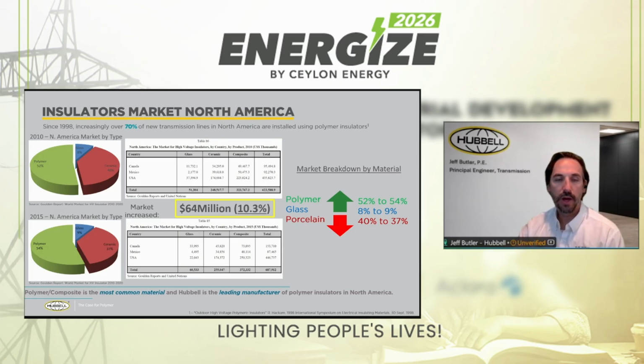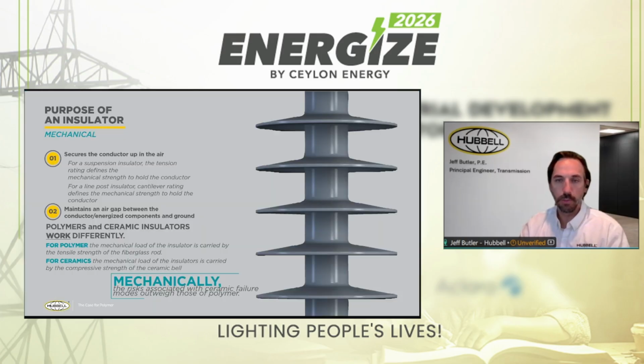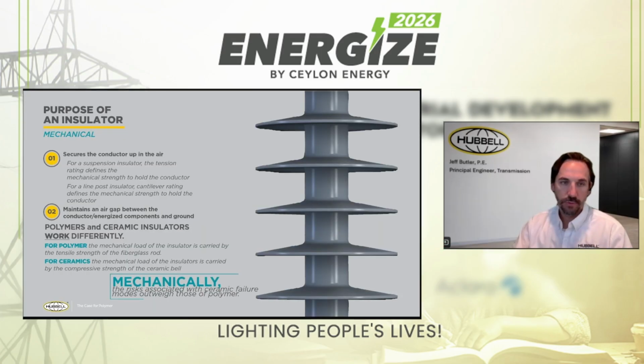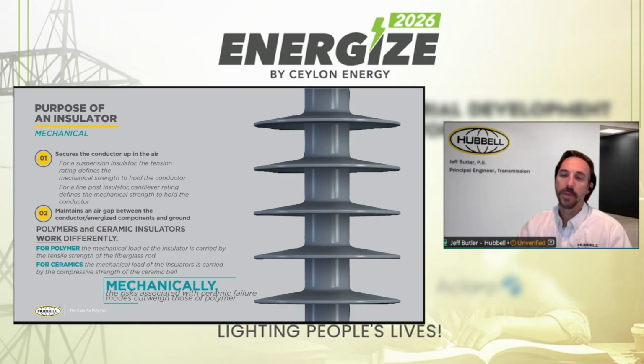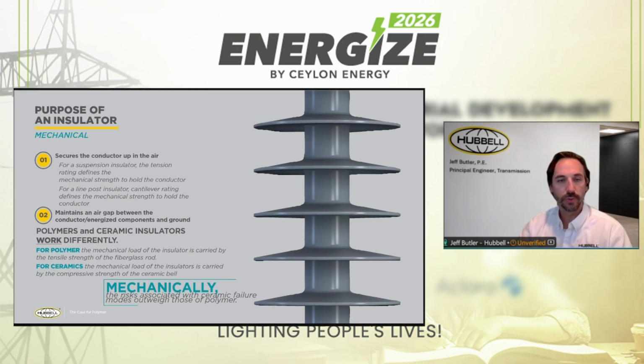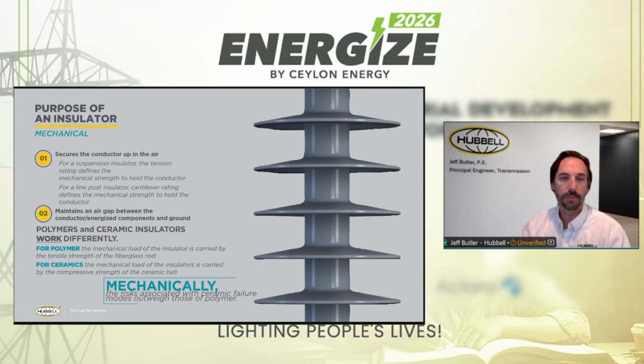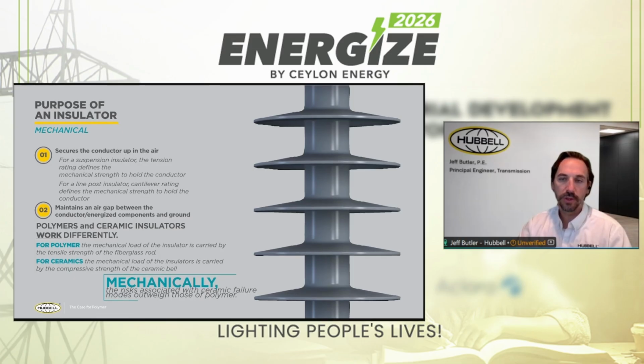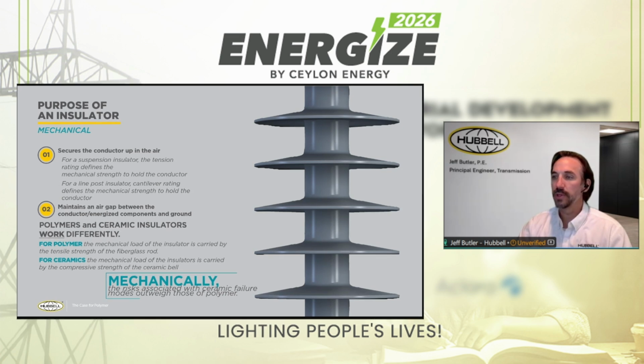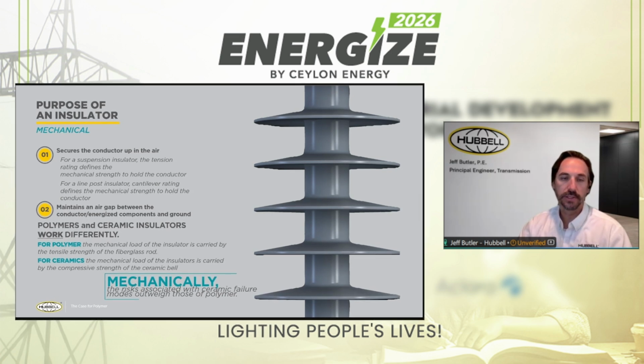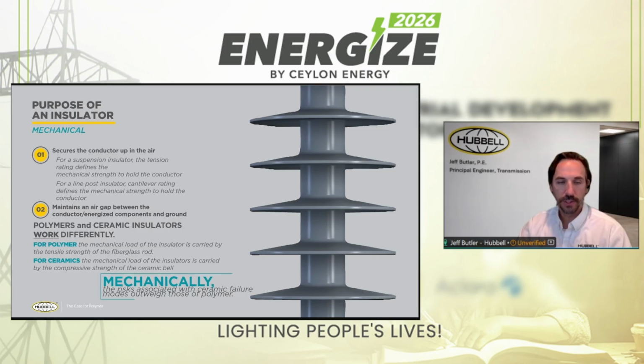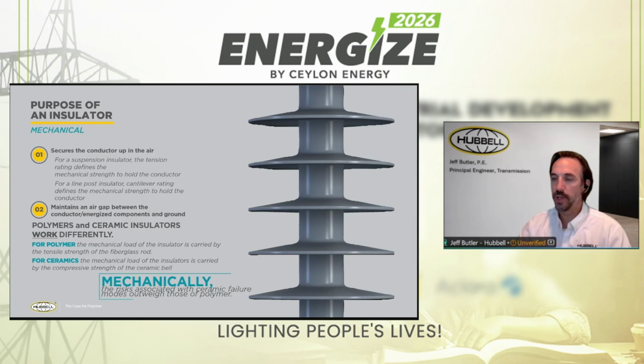So let's talk a little bit about polymer insulators just to make sure we're kind of on the same page. These are often referred to as composite insulators. Composite just refers to two materials that come together to differentiate those from ceramic insulators where you have a porcelain or a glass bell type. But the purpose of an insulator, no matter what the material is, is the same. So mechanically, they are to keep conductors up in the air, maintain clearances, maintain distances, hold lines where they're supposed to be.